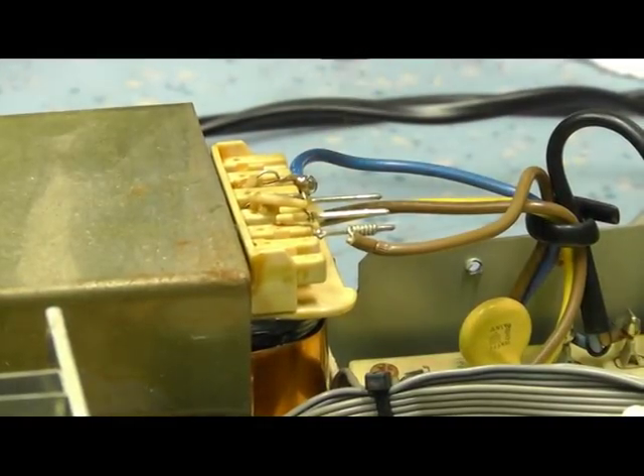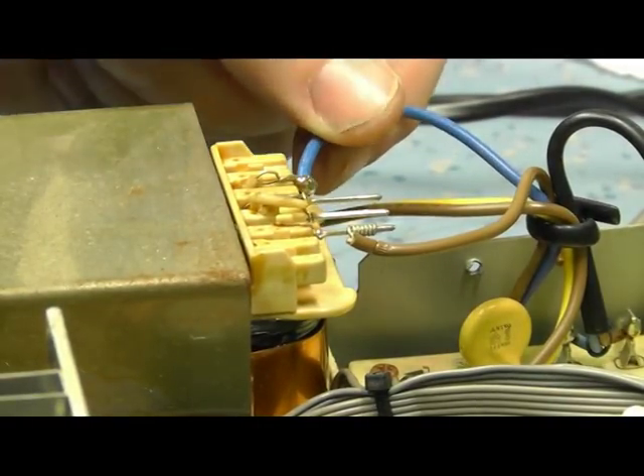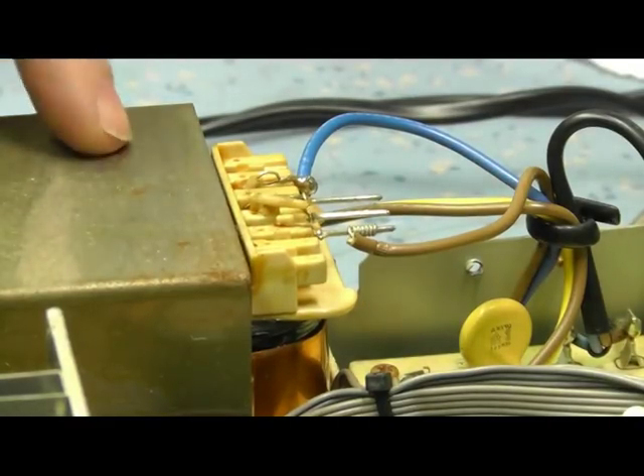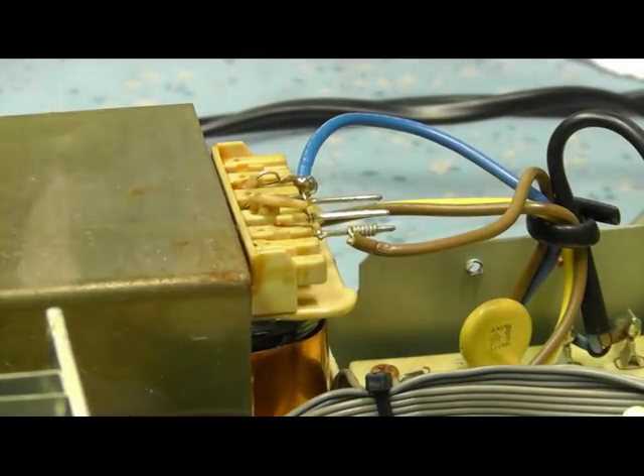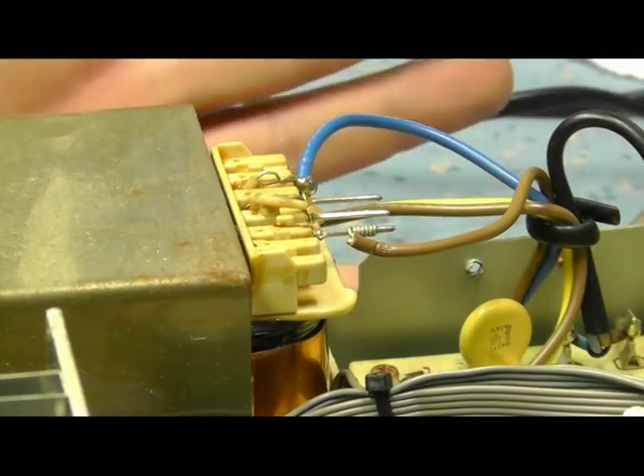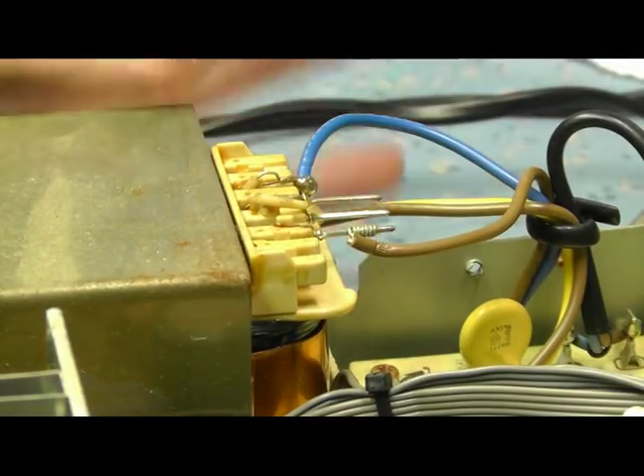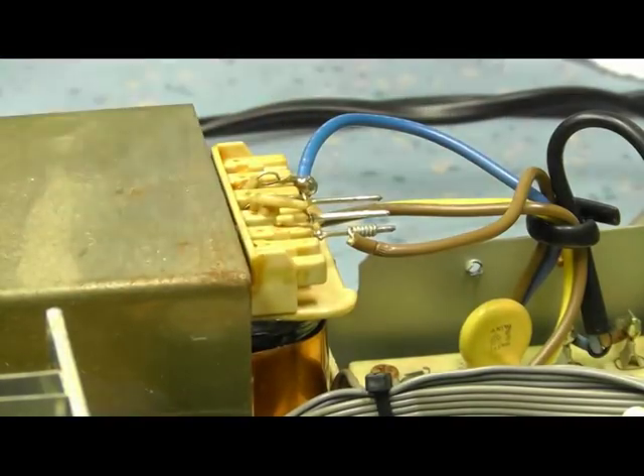Okay, what I've done is gone across the two outer tappings of the transformer, and I've got about 17 ohms there. Now, I don't recommend anyone doing this - this is not the approved method of fixing a transformer. This transformer has failed because it's got too hot.